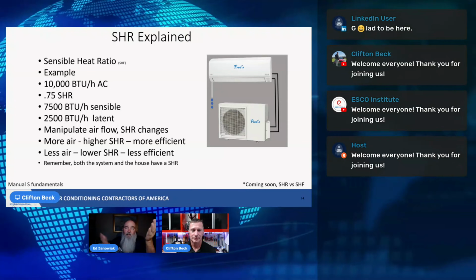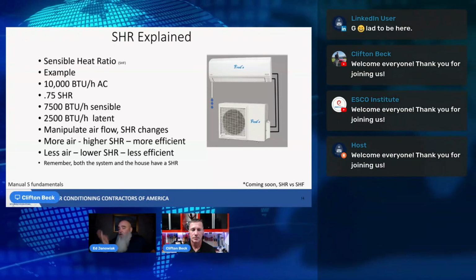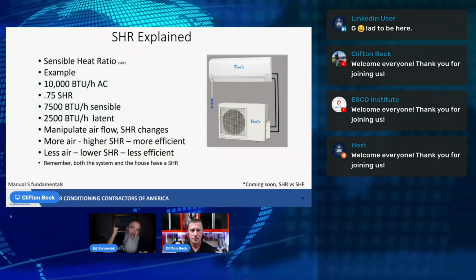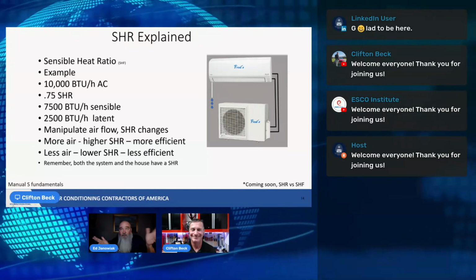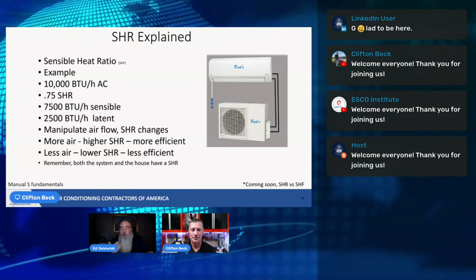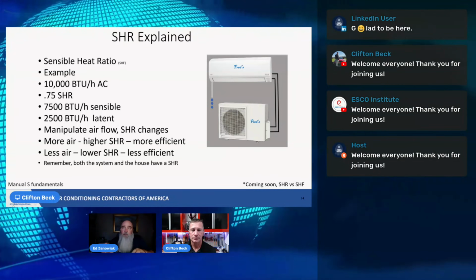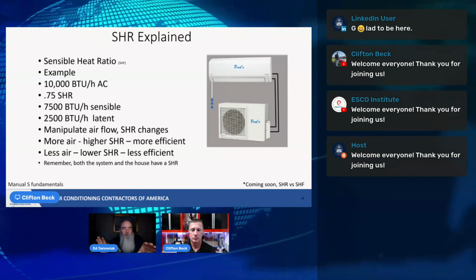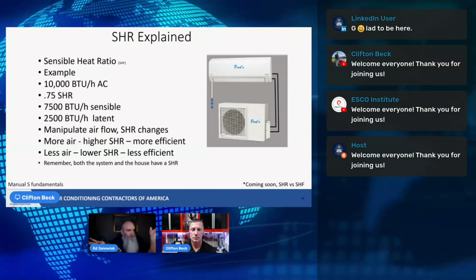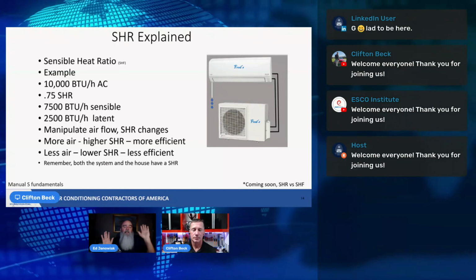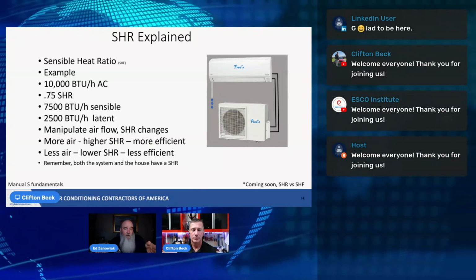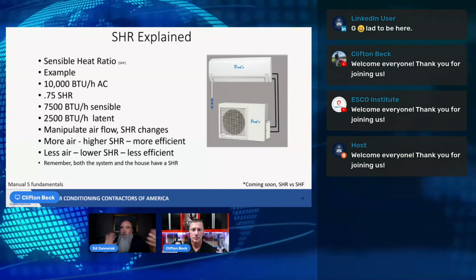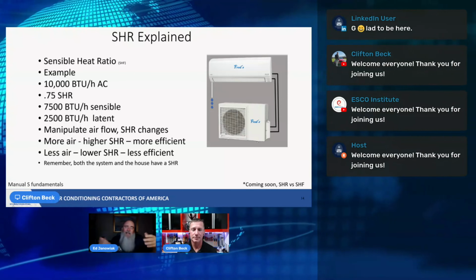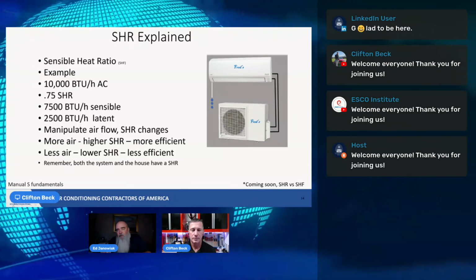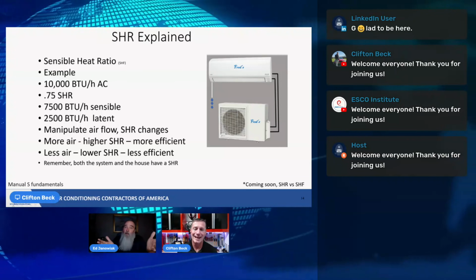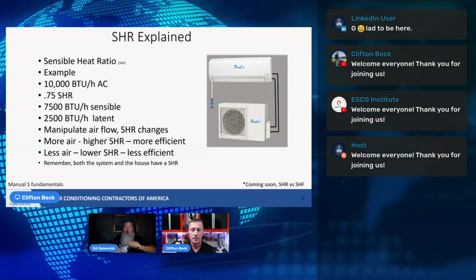In the example on the screen, that's a 10,000 BTU unit. And if you're going to tell me that doesn't exist, I'm going to say it does. And it's a Fred's unit right there in front of you. All right. So it's 10K. I picked a sensible heat ratio of 0.75. And I picked 0.75 because if you took your favorite unitary split, 14, 15 SEER, standard piece of equipment, and ran it at that magic 400 CFM per ton, it would produce a sensible heat ratio around 0.75. Approximately. Yeah, it might be up to 0.77. It might be down to 0.73. Sure. That's the fundamental design behind it. Yeah, yeah. And it's a ballpark rule of thumb.